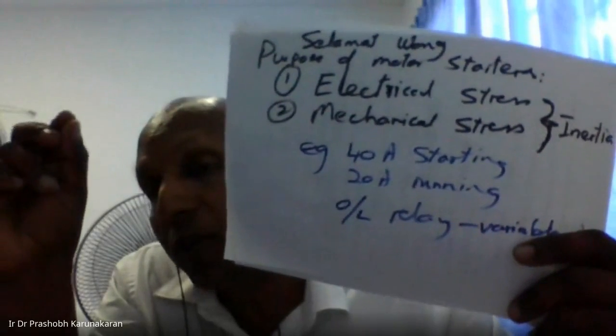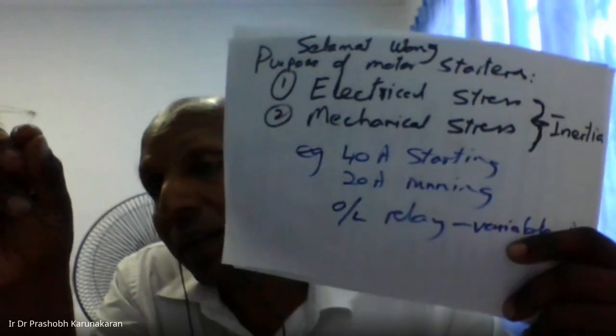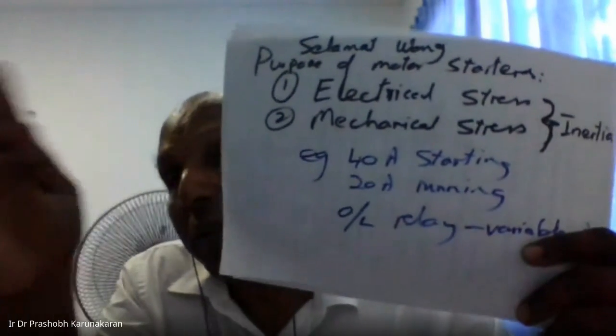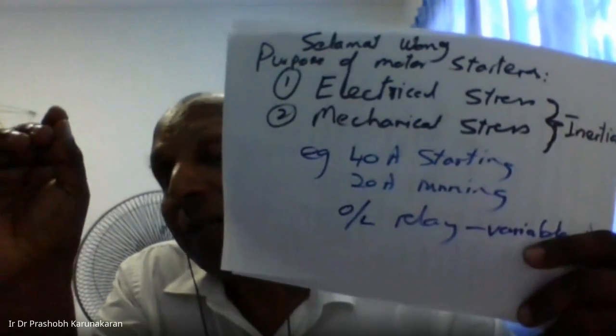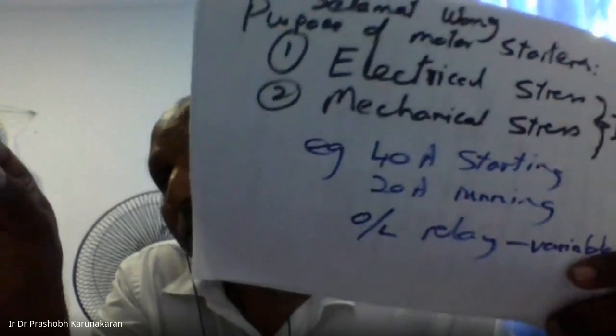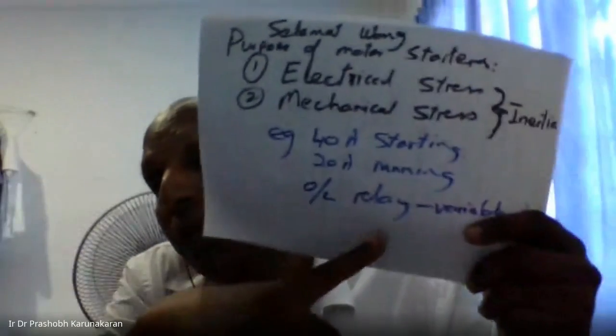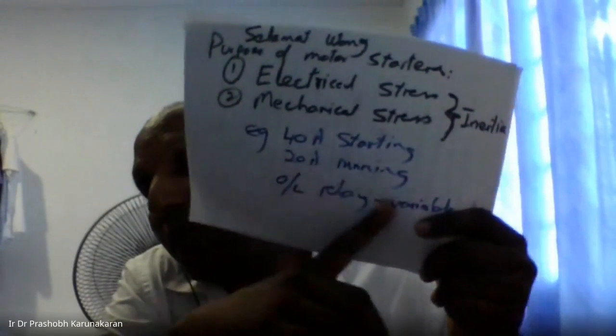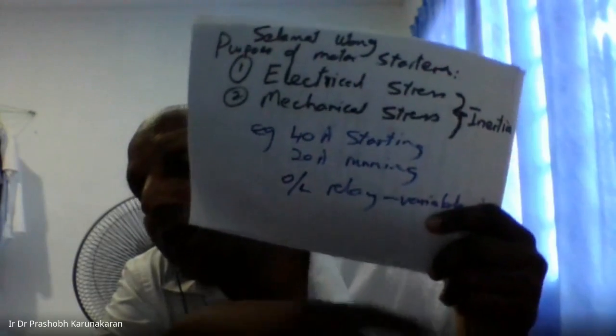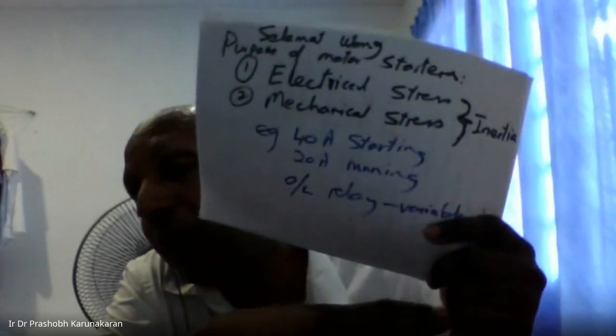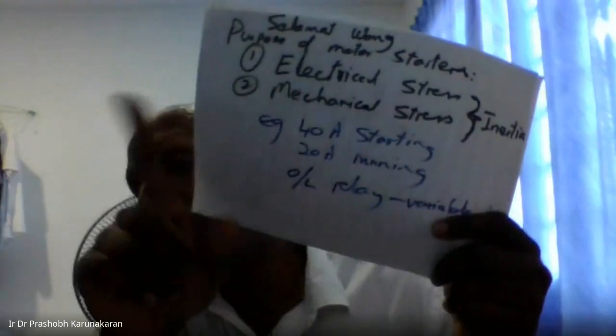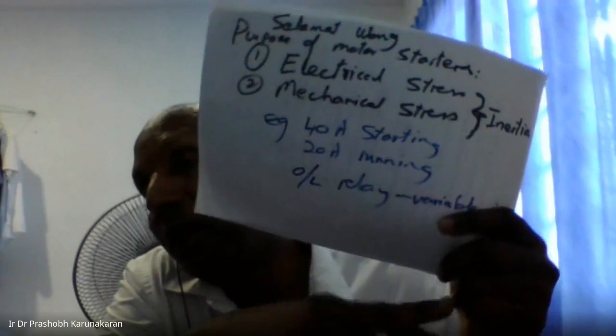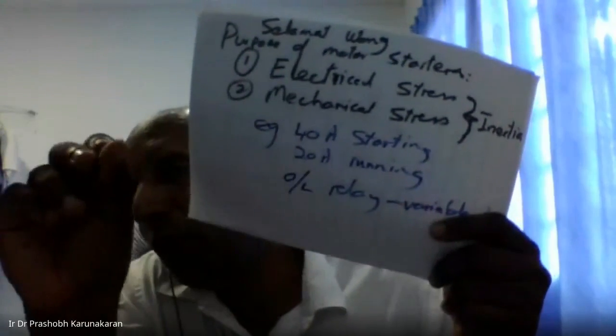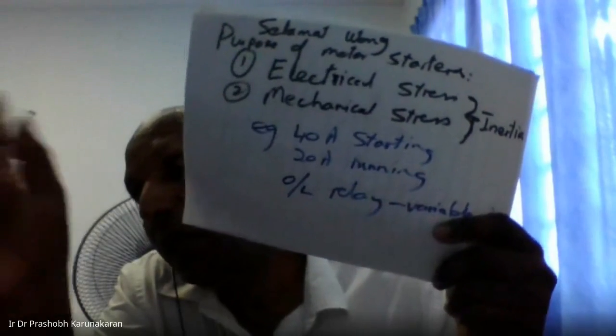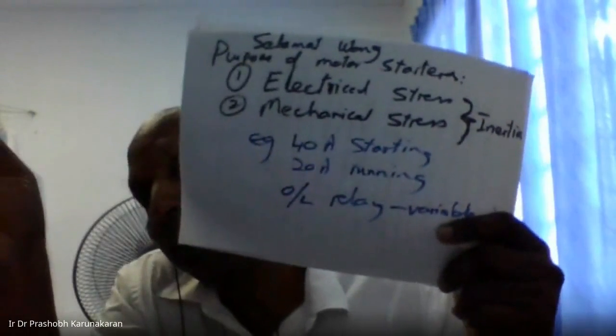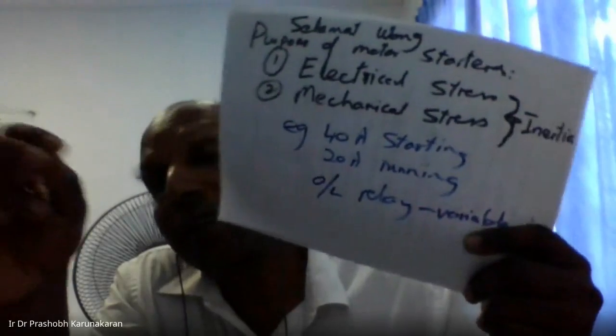The MCB in the house works almost exactly the same way as the overload relay. They use a bimetallic strip, but the MCB is fixed amp. If it is fixed, say you put a 20 amp MCB to start a motor, it cannot start, because starting you take 40 amp for 6 seconds. So the motor will never start. The circuit breaker will always trip. That's why you need 40 first. You tune it to 40, and after it has started, you tune it back to 20. Understand?